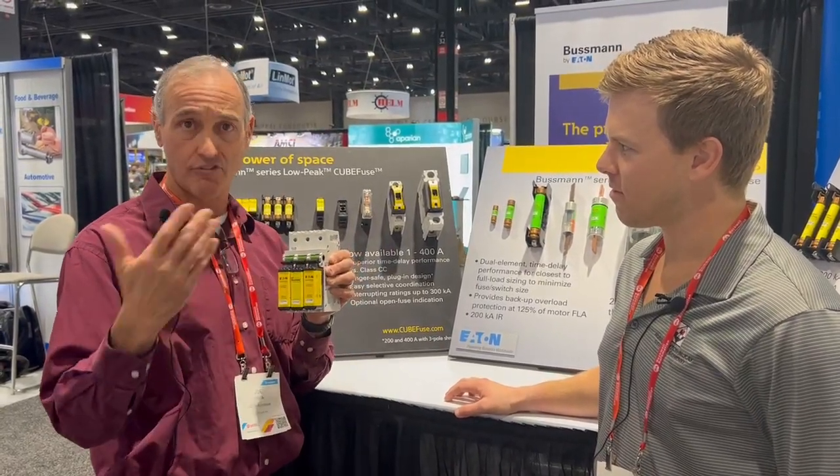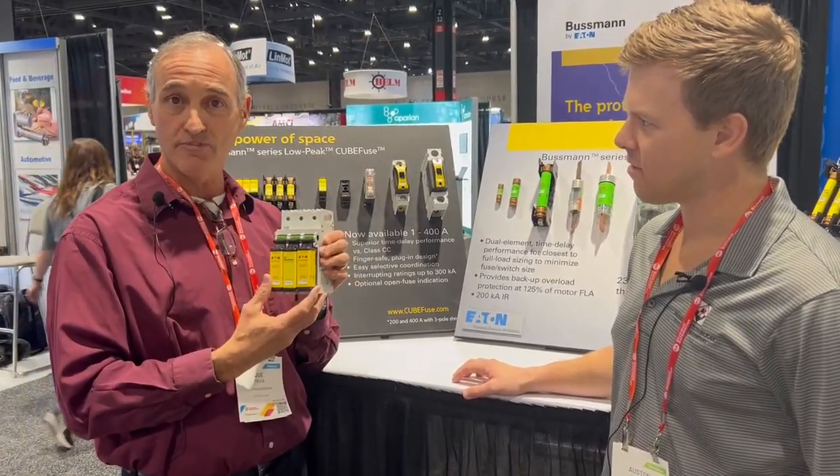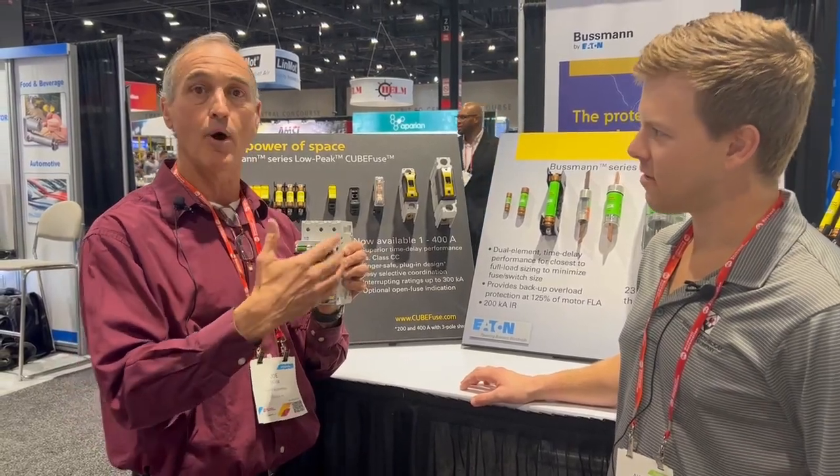If you mount it outside the panel, now you've got low arc flash or incident energy level to handle all of this. So this is the new CubeFuse — we can supply 30, 60, and 100 amps, and we go up to 400 amp disconnects.